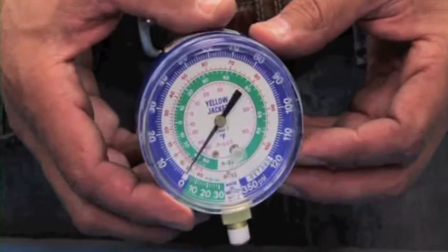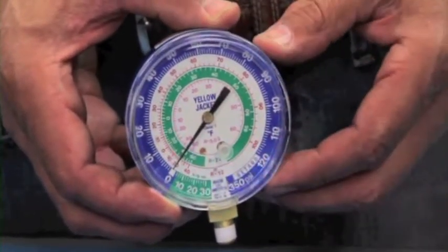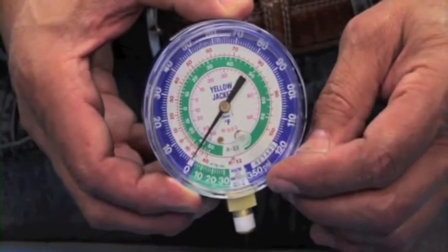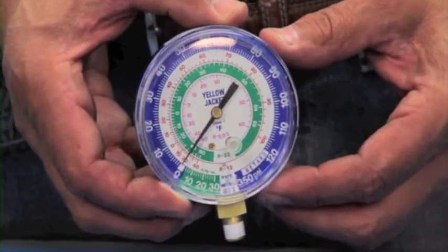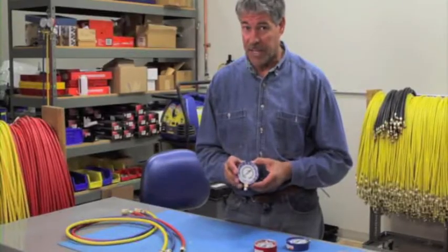For example, here's a compound gauge with a working pressure of 120 psi, which is the highest measurable pressure. When the needle goes beyond 120 psi into the retard zone, the actual pressure is unknown. If the pressure rises higher than 350 psi, the gauge is likely to be damaged.